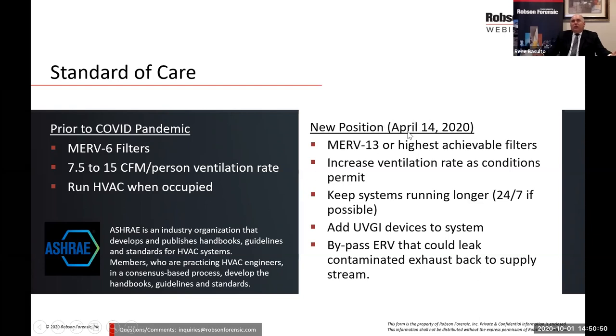The new position paper, which was issued April 14th of 2020, just right after we understood what was going on with the pandemic, says, and this is from the position paper, MERV 13 or the highest achievable filters that you can install on your system. Remember, we're talking about the limitation of the system. It could be that you can't get a 13 in there. I actually ended up putting 13 filters in my house and in the office.